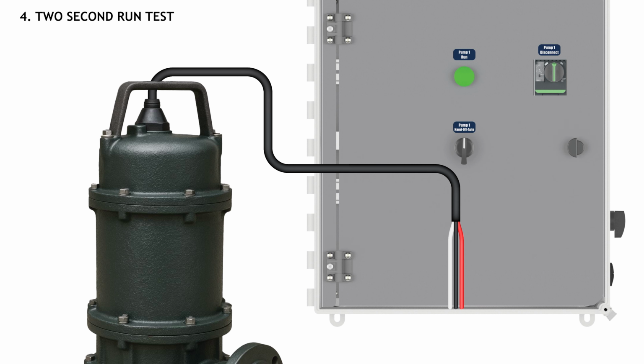If the amps jumped significantly higher than 15, say 30 or 40 amps, and the pump hums, then stop immediately and do not try to restart the pump, as troubleshooting must correct the problem. Retrying without fixing the problem will only lead to pump and panel failure. In another video, we can show how to troubleshoot the control panel.